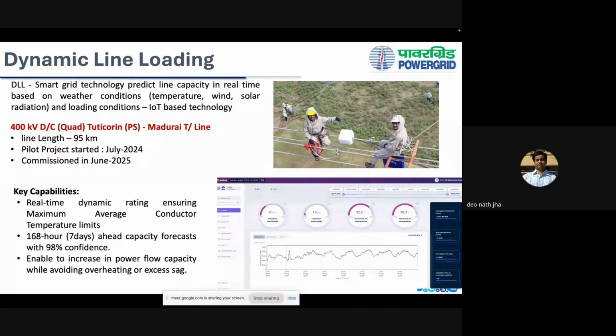But now with the introduction of dynamic line loading, the more power you send across a transmission line, theoretically the more loading is on the line, the sag will increase and the transmission conductor distance from the ground will decrease. But what dynamic line loading enables us is to get real-time environmental conditions across the line. So if the ambient temperature is very low, if the wind speed is very high, then the power flow across the line can be increased, and we also get real-time updates on the sag, or the distance from the ground, and based on that we can continuously increase the power flow across the line till a threshold level.